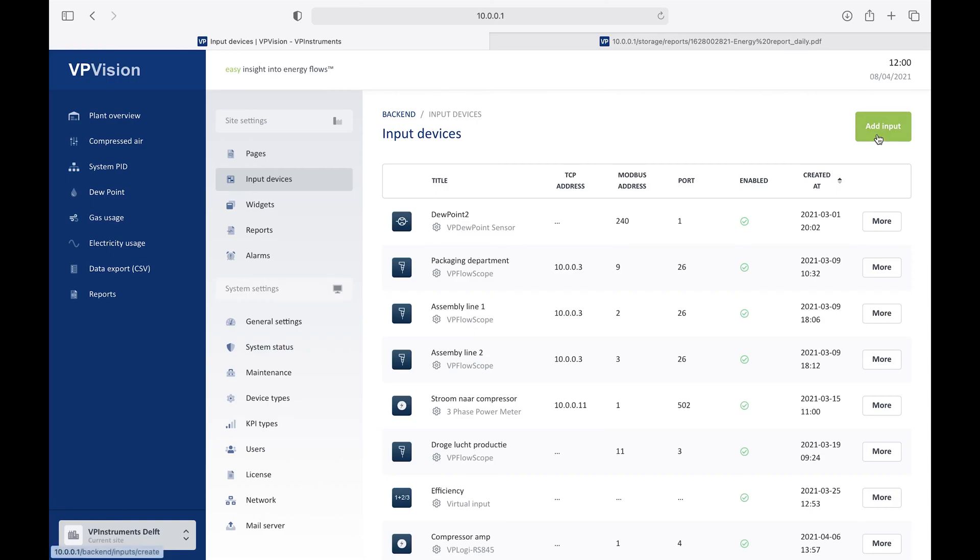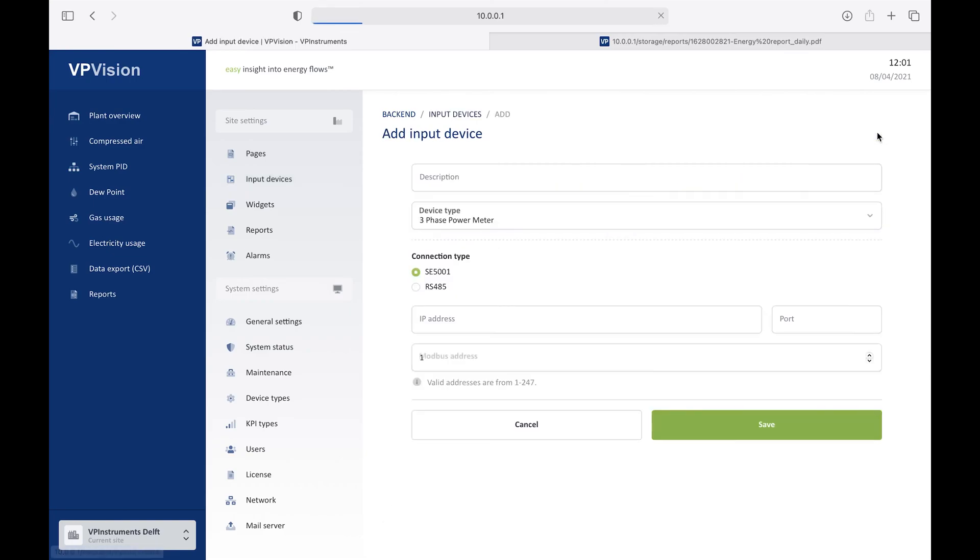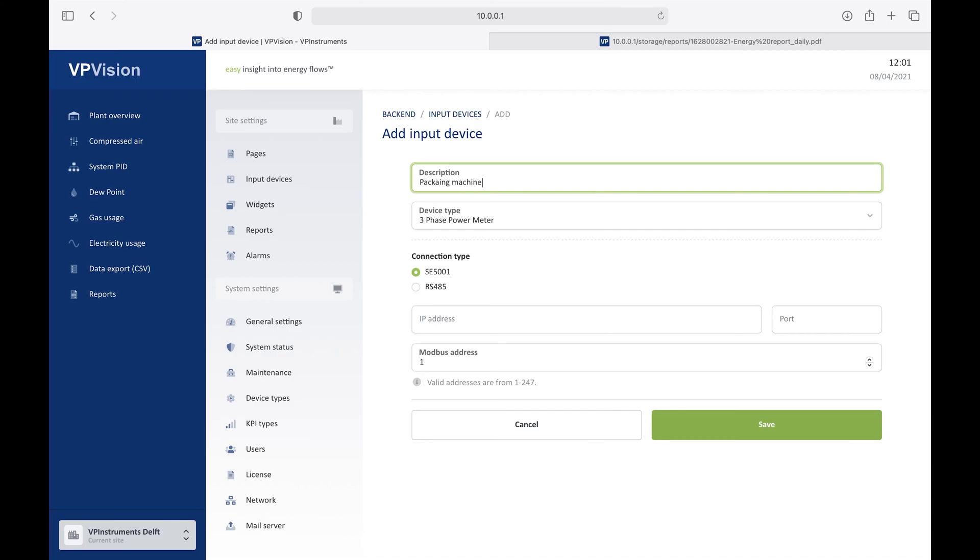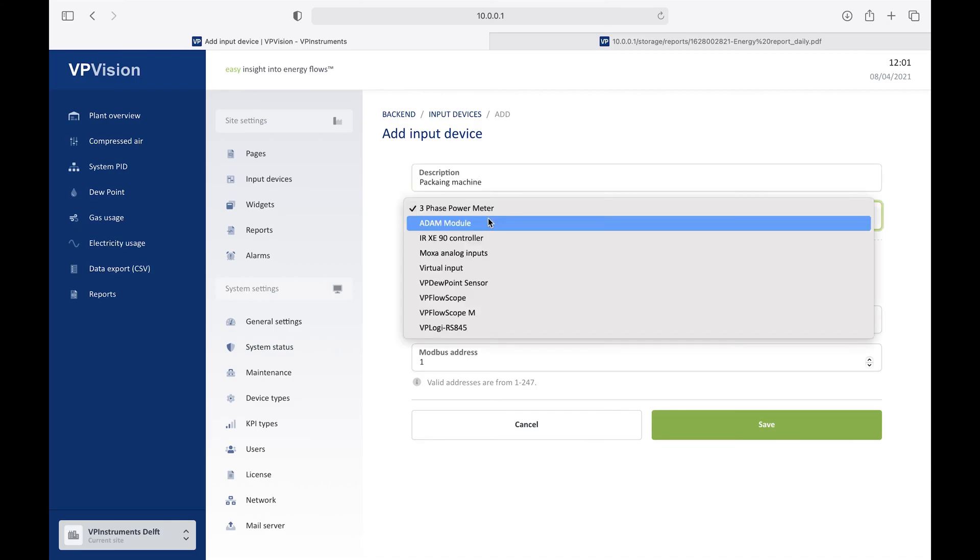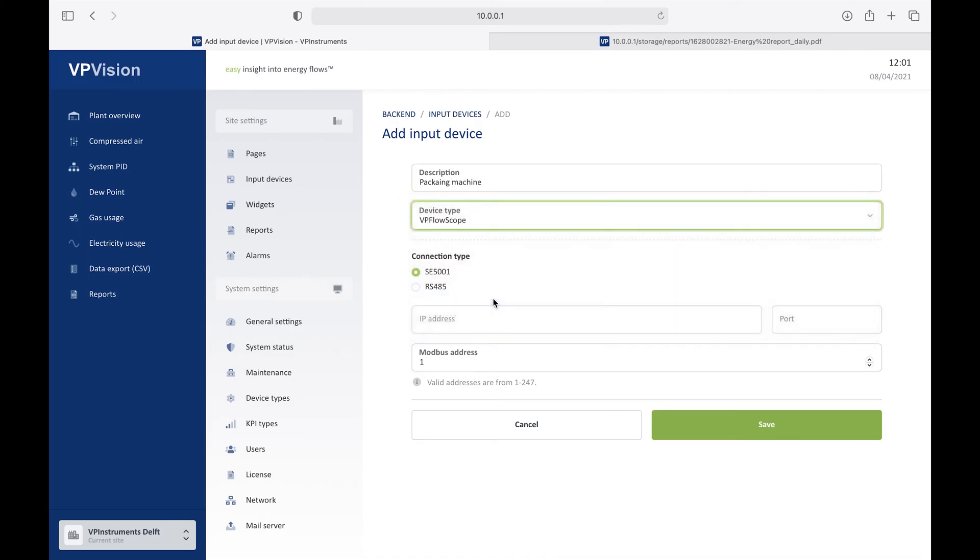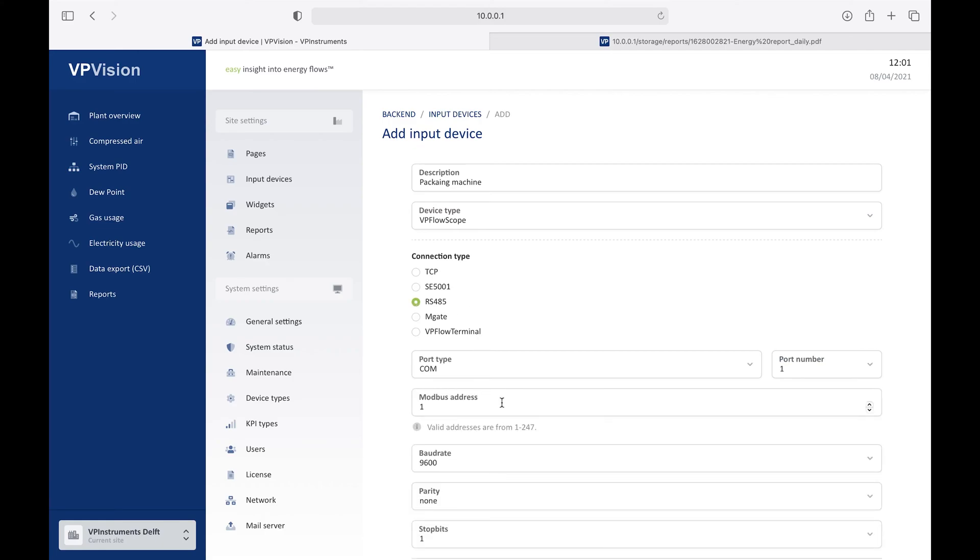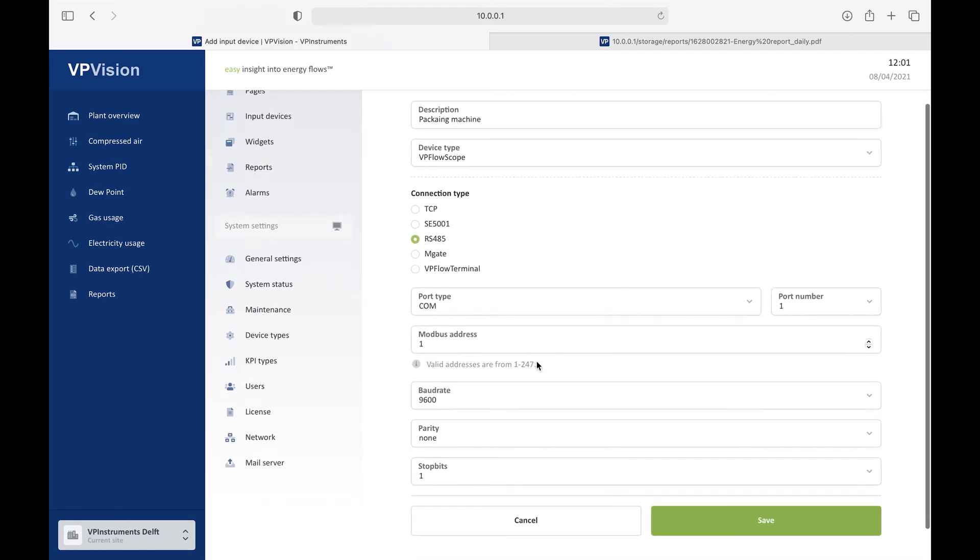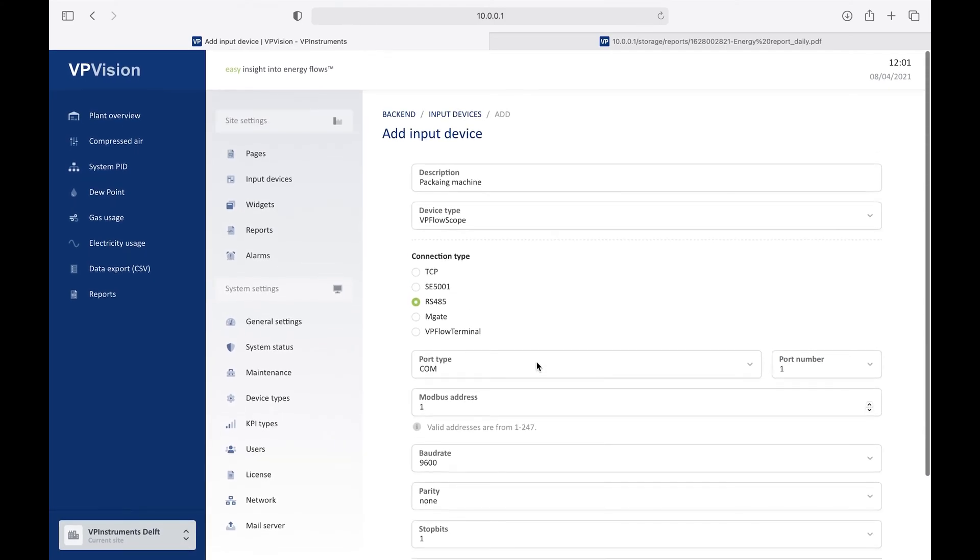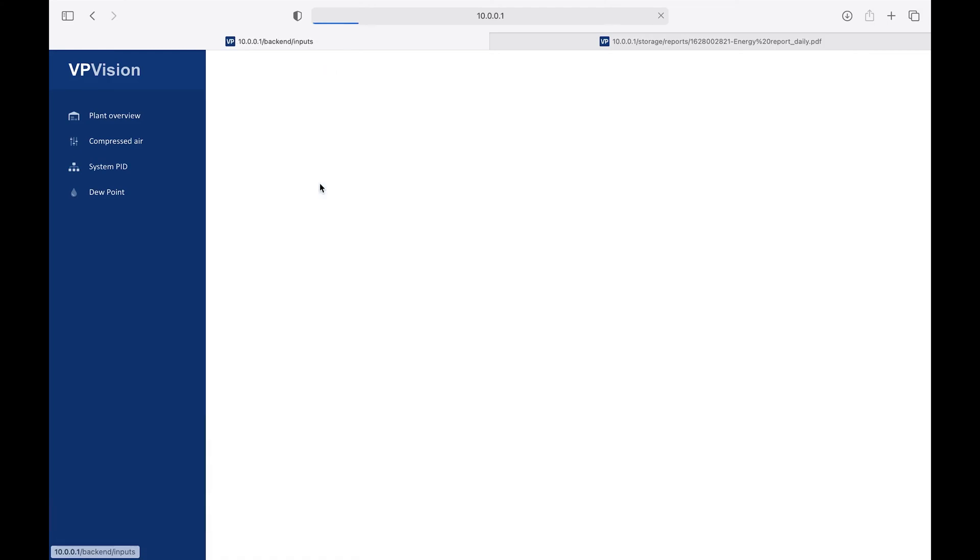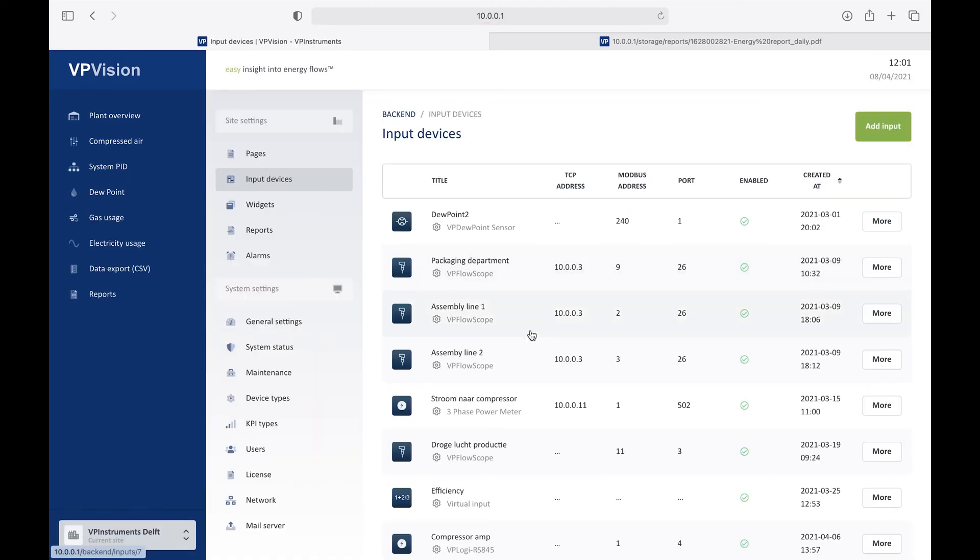If you want to add an input device, then you click on add input, and you will get a dialog screen here where you can describe the input. So for example, it's another packaging machine you just purchased. And it's another flow meter in that case, FlowScope. And here you can set the connection parameters, like the IP address or the RS-485 communication settings, and then basically add the sensor to the list. You can have a clear overview here again of all those inputs that are already active.